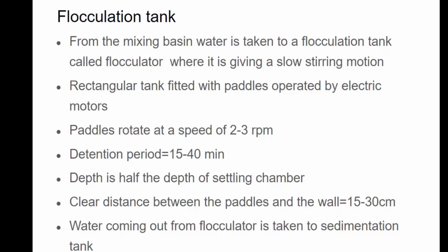This is to allow the particles to agglomerate and increase in size, so the settling will be faster. The detention period for the flocculation tank will be 15 to 40 minutes. That is, one water particle that enters the flocculation tank will flow through it and come out after 40 minutes. The depth is half the depth of the settling chamber. All these values are very important while designing a clariflocculator.